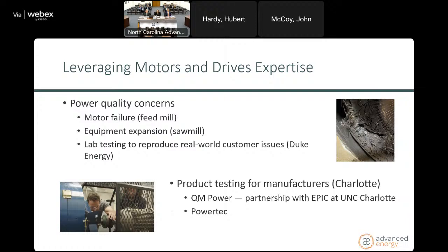Oftentimes there are things customers can do on their side to mitigate power quality problems. I have a couple of examples. One was a feed mill experiencing failures of 600 horsepower motors—these are really large motors. I asked one of our employees for a scale comparison, and he said it was about the size of a riding lawnmower. A picture of the failed motor is shown on the right.